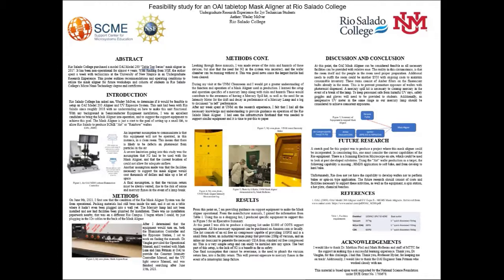I was able to adapt a form that UNM uses for the calibration of the UV light source. This is necessary as often a UV light source will need its voltage increased through its life cycle to maintain the same intensity. This form should accompany the UV intensity meter, as it can be used to ensure a uniform exposure intensity and to allow as-left values to be recorded when changes are made to the UV directional lenses.